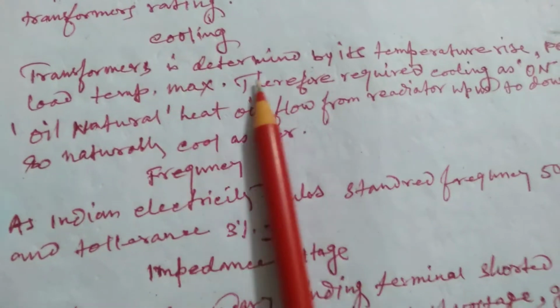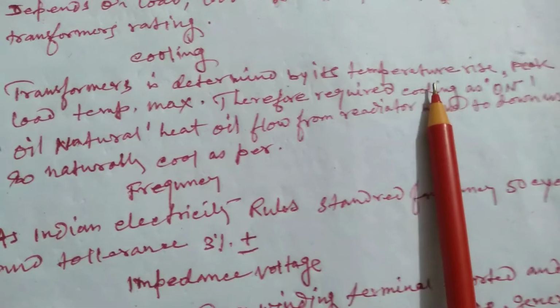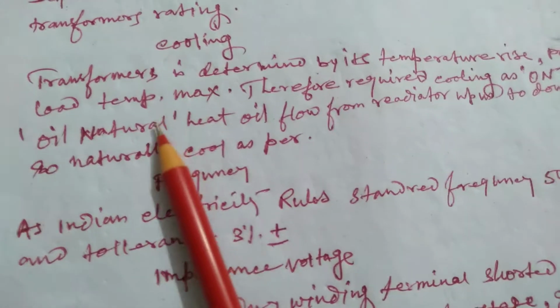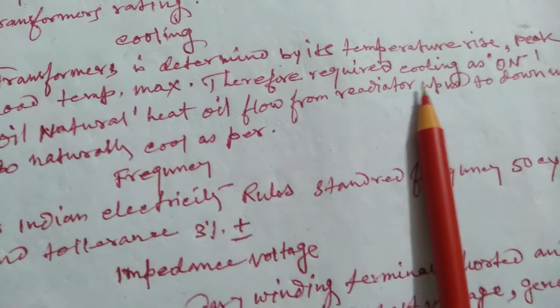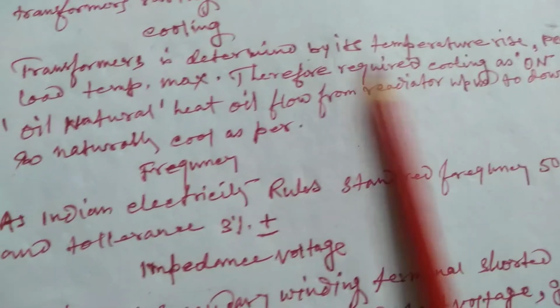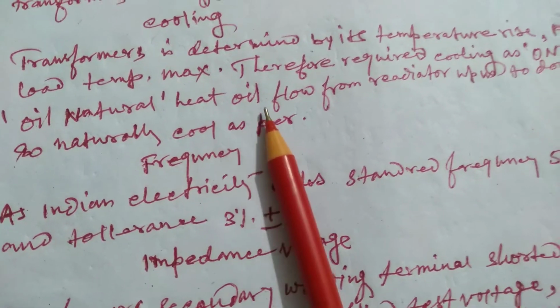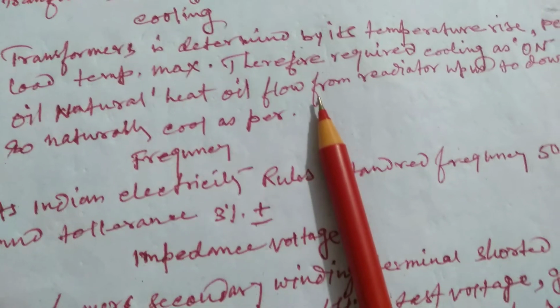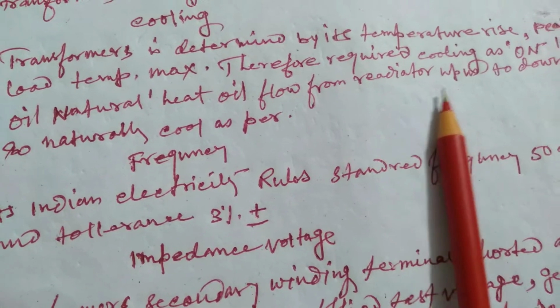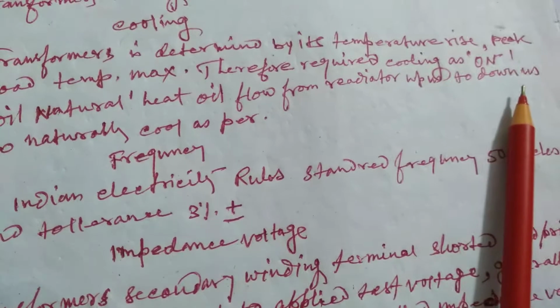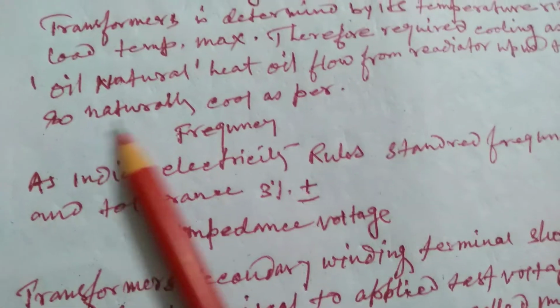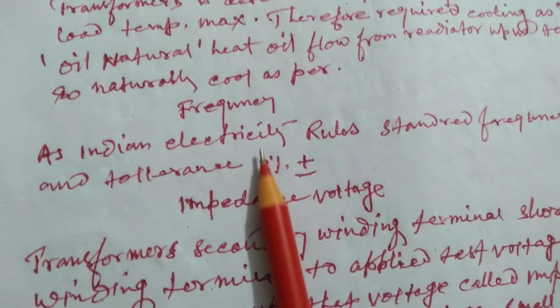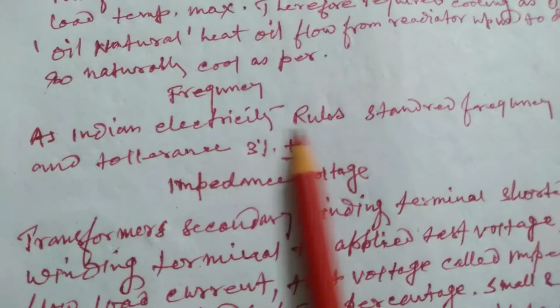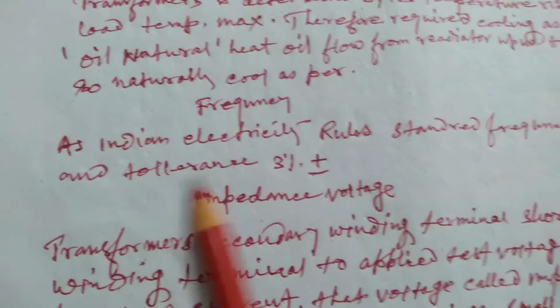Cooling: the transformer is determined by its temperature rise, with peak load giving maximum temperature. Therefore, the required cooling is provided. With oil natural cooling, heat in the oil flows through the radiator from top to bottom, so it cools naturally. Frequency, as per Indian electricity rules, is standard 50 cycles with tolerance of plus or minus 3%.